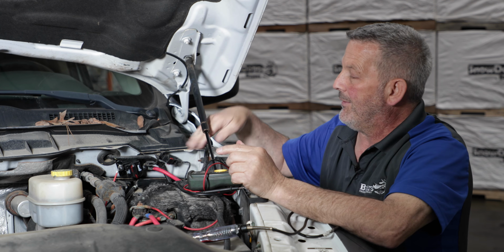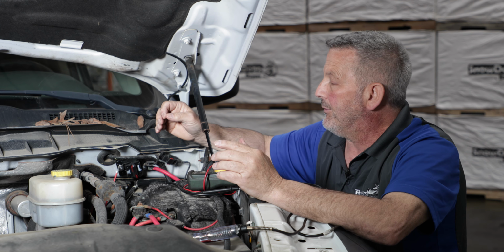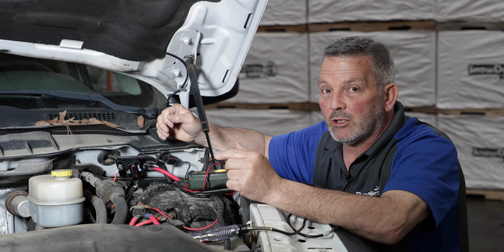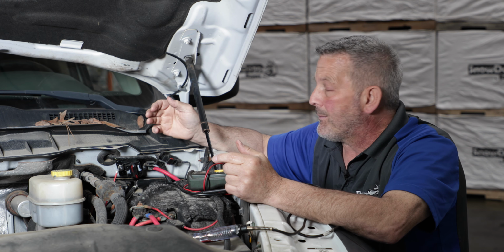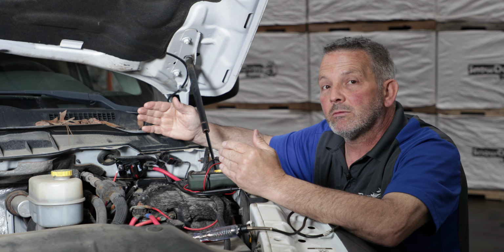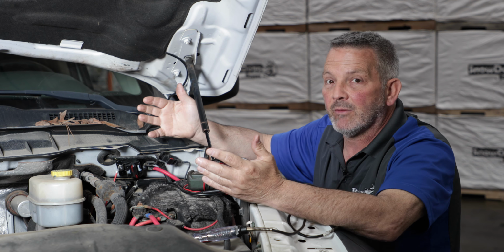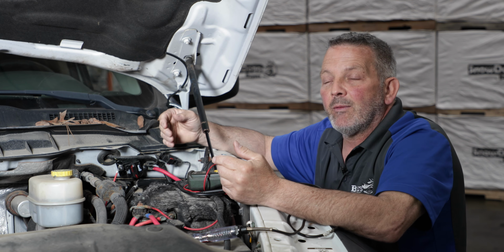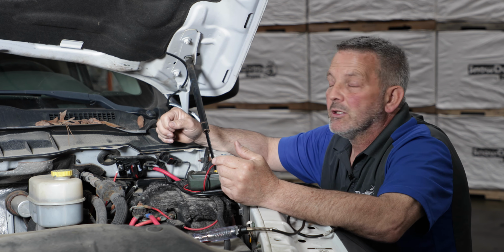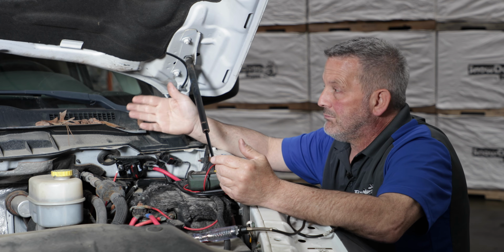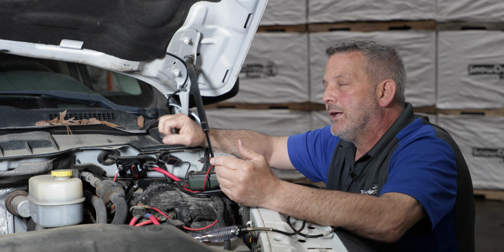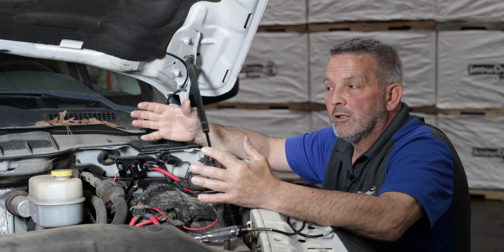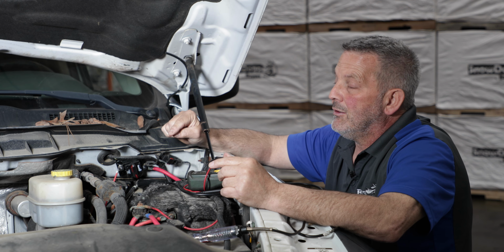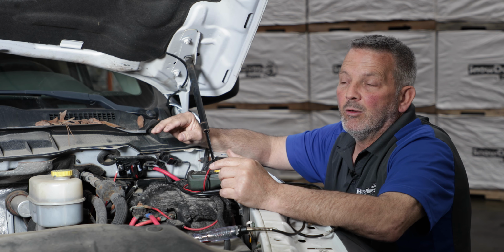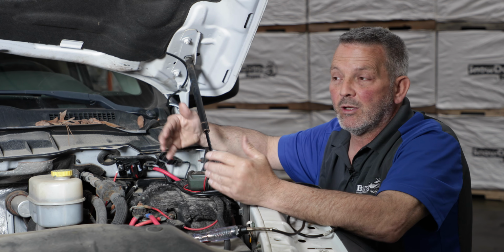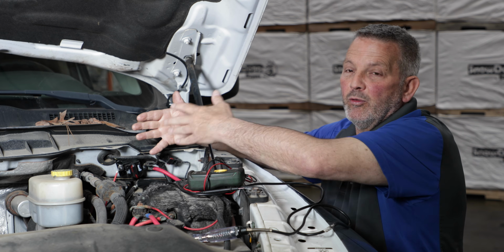That's probably one of the final tests we're going to do to diagnose the spreaders we talked about in the opening comments. First, test the motor and back, because that's what makes everything move — same thing with the vibrator, test it back there with a separate source. Second, test it right outside the controller, put power there, get it back there, and make sure that's working. If that's working, and the controller is getting power, most likely the controller could be bad. So that's what we're testing, as long as we know we're getting power to the controller.